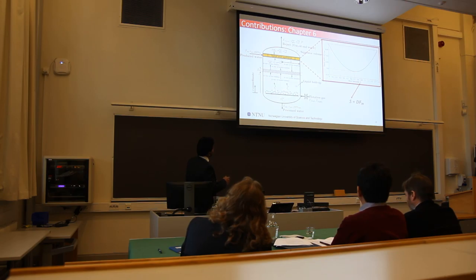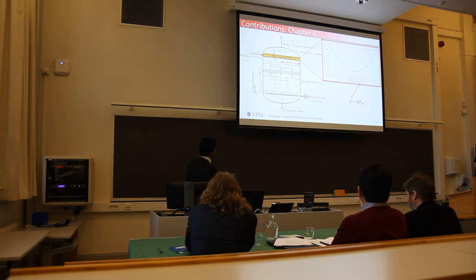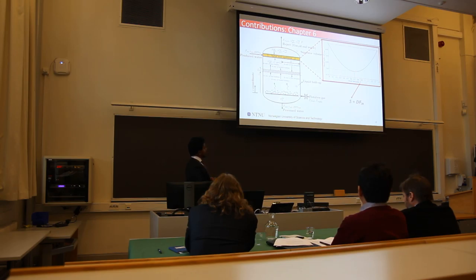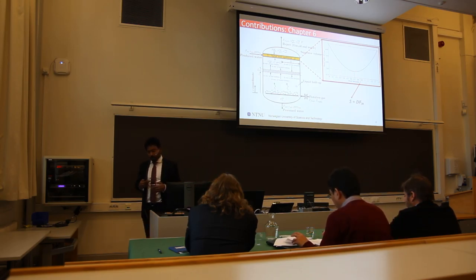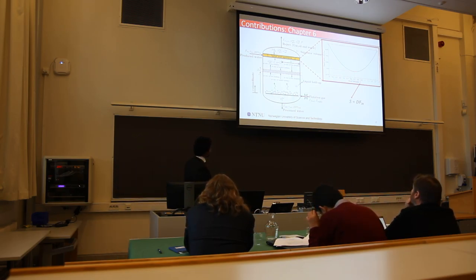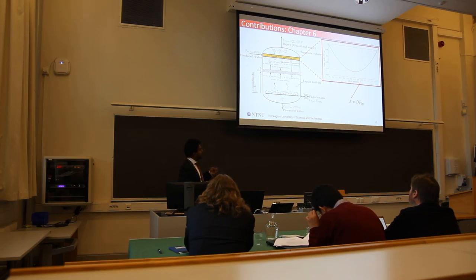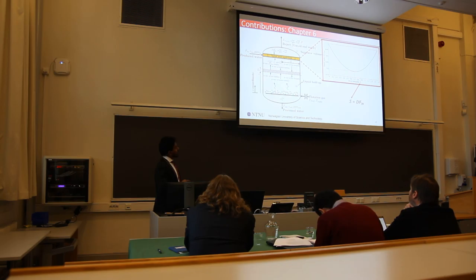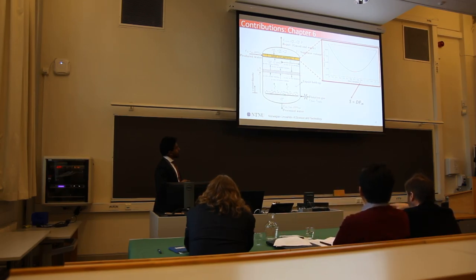Free bubbles start at the bottom and travel upward. In each control volume, we write down the mass balance: free bubbles in and out, loaded bubbles in and out, and oil droplets traveling downward. At the bottom, the droplet concentration gives the ppm count in the clean water. There is also a reject stream at the top containing gas, oil, and some water.